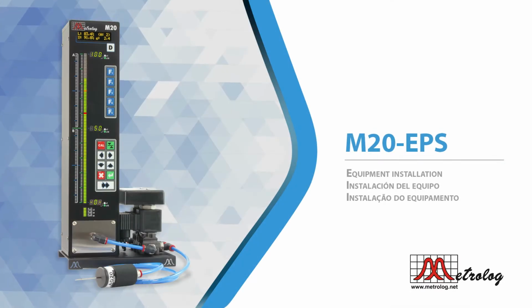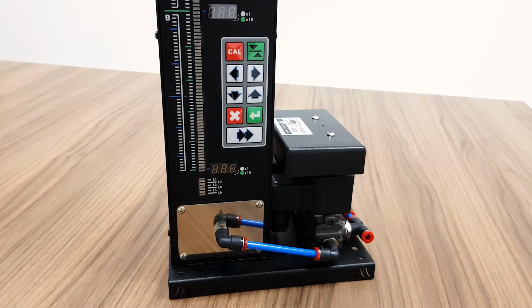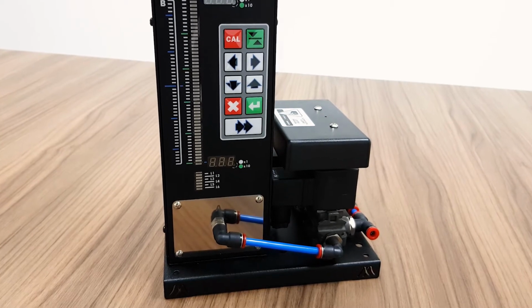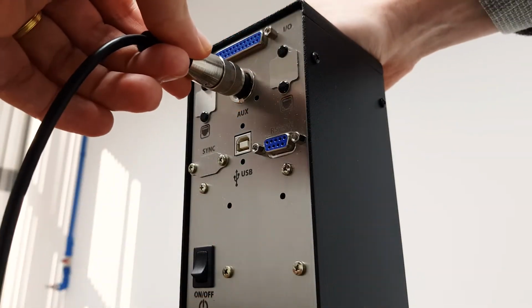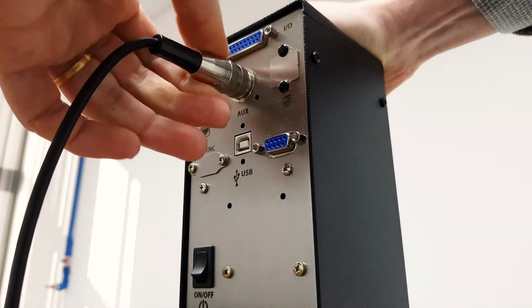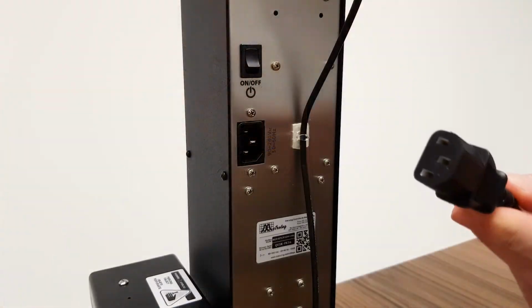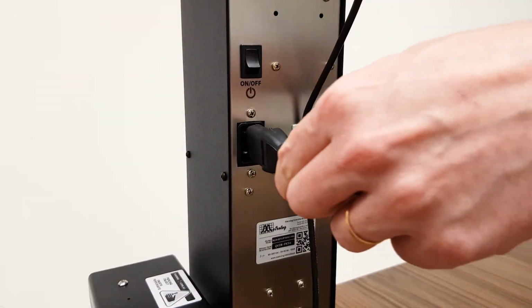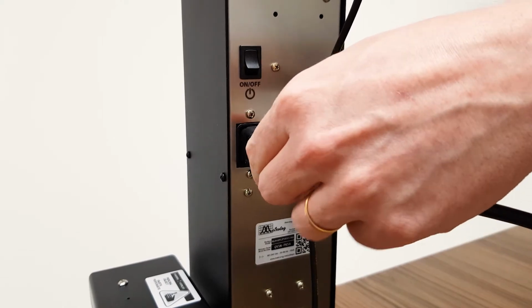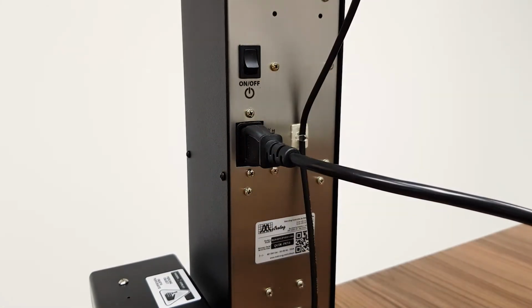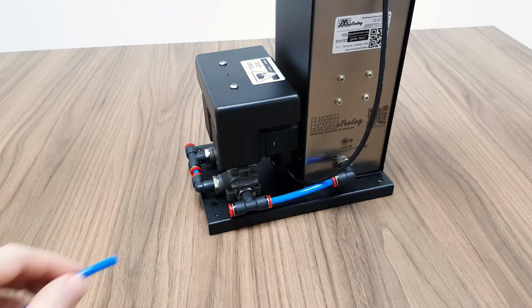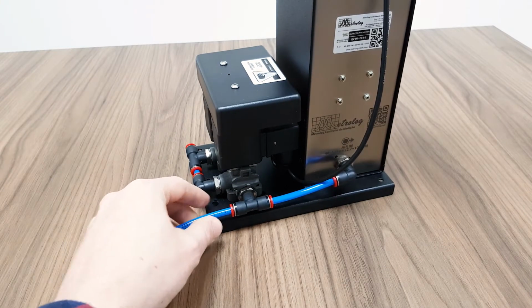Installation. After unpacking the product, position it on the measurement bench. On the rear panel, fit and thread the circular valve automation connector. Also connect the power cable, plugging it into the AC mains, voltage between 80 and 240 volts. Finally, connect the compressed air supply to the equipment.